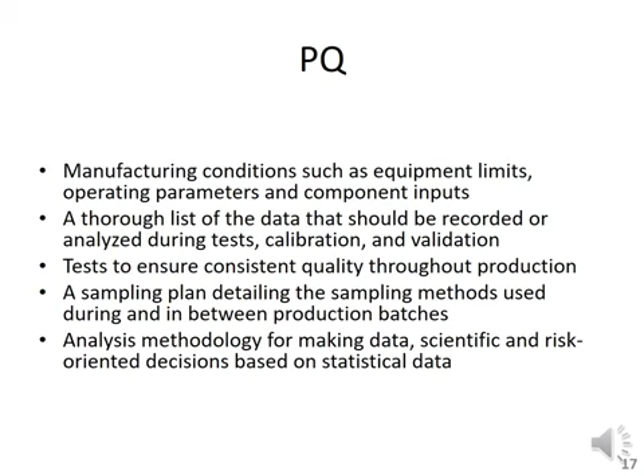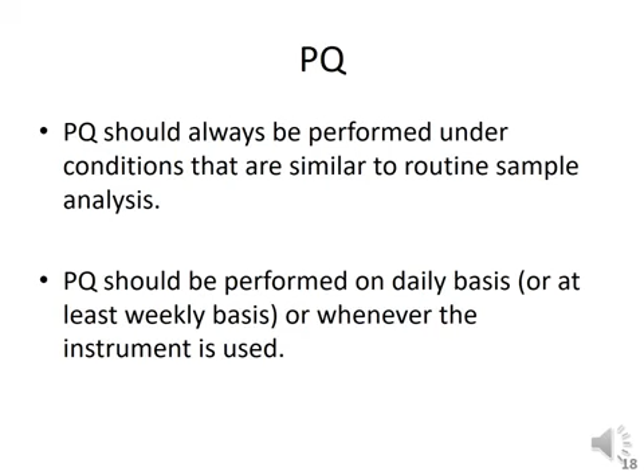Now, the performance qualification PQ should always be performed under conditions that are similar to the routine sample analysis. That means it is important that you do your performance qualification under conditions similar to the routine sample analysis. If you do it under somewhat different conditions, it will not be worth working on, right? Performance qualification should be performed on a daily basis or at least weekly, or whenever the instrument is used. If the instrument is not in use daily or weekly, whenever you use the instrument you have to do the performance qualification and keep the record of it, and it will help you in maintaining the instrument for a longer time. Okay.